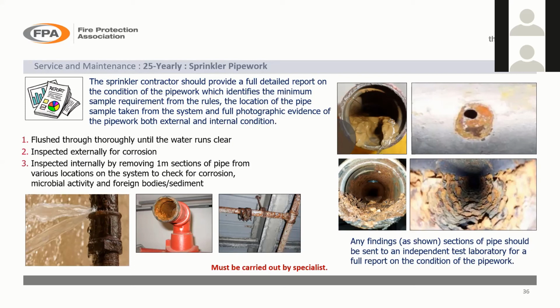Those examples on the right hand side there, they give you an example. Not very nice to look at, but they are the extreme. Quite a lot of times you look inside a sprinkler pipe, it's actually not too bad, to be fair. But equally, if you do find this, there could be reasons for it. It could, of course, be that your pipes are in a corrosive atmosphere, or the processes beneath it are corrosive. You need to check that.